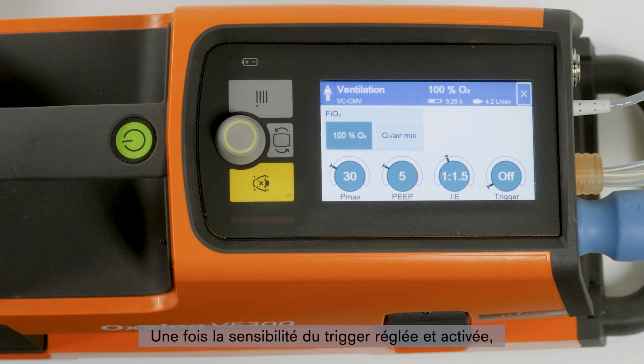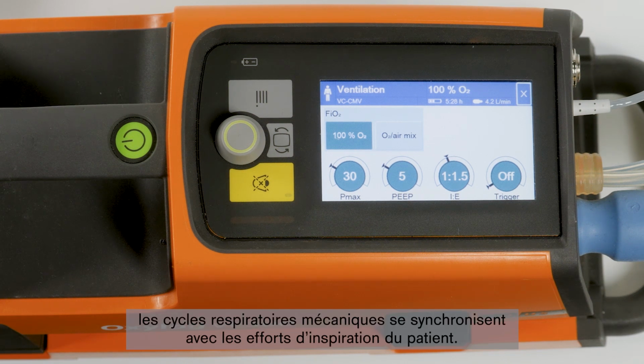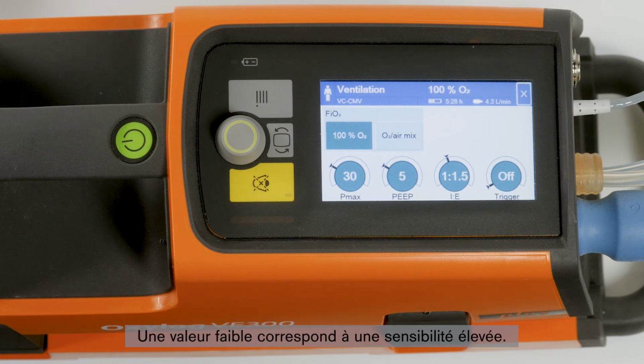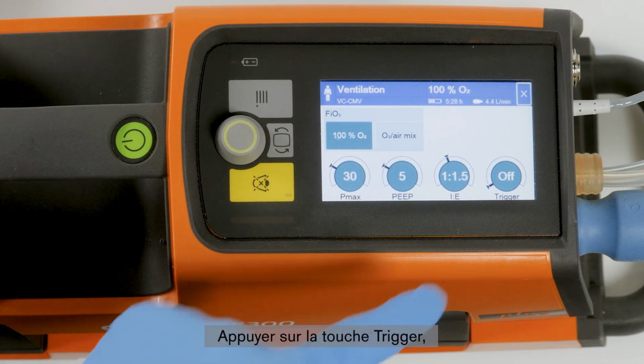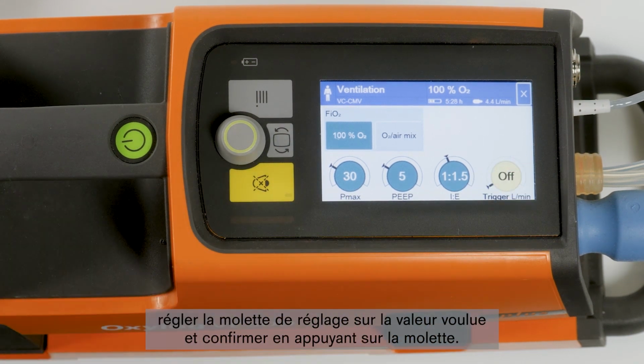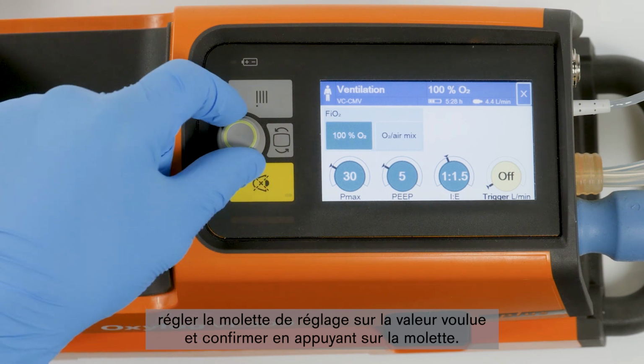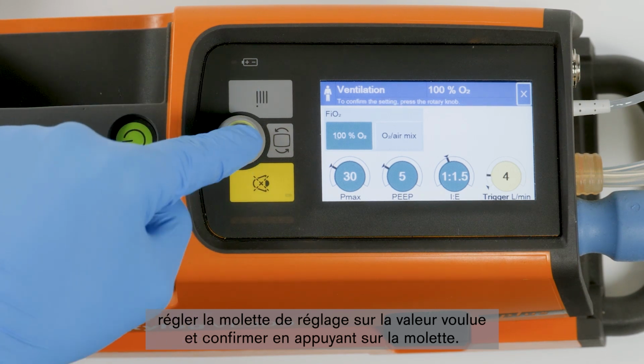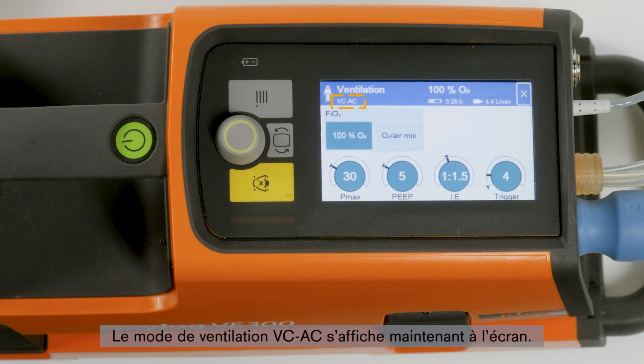When the trigger sensitivity is activated and set, the mandatory breaths are synchronized with the patient's inspiratory efforts. A low value corresponds to a high sensitivity. Touch the button Trigger. Turn the rotary knob to adjust to the required value, and confirm by pressing the rotary knob. The ventilation mode VC-AC is now displayed on the screen.